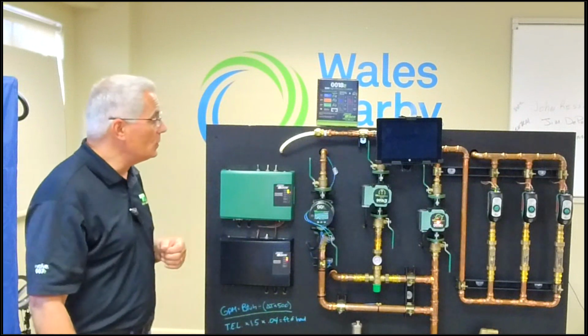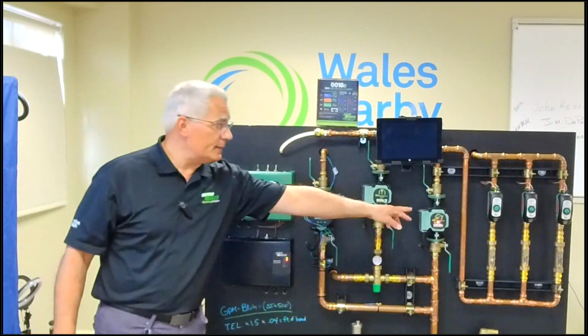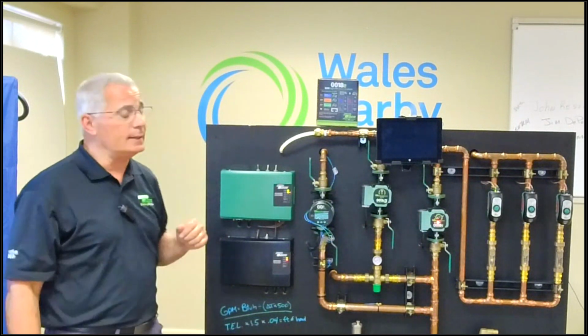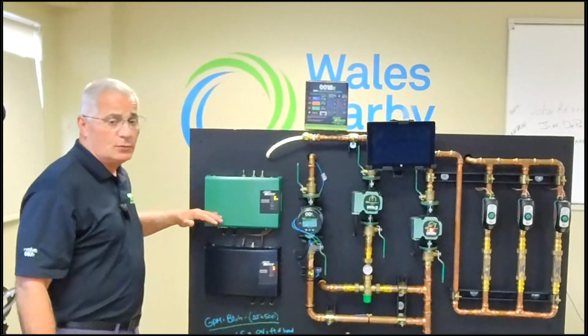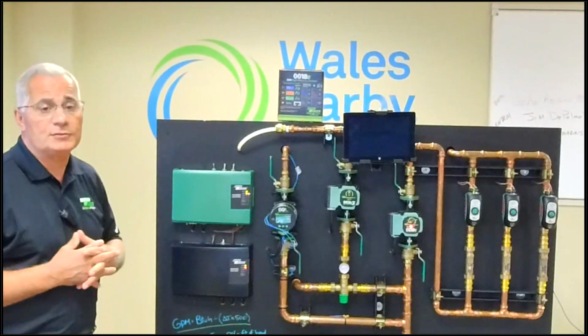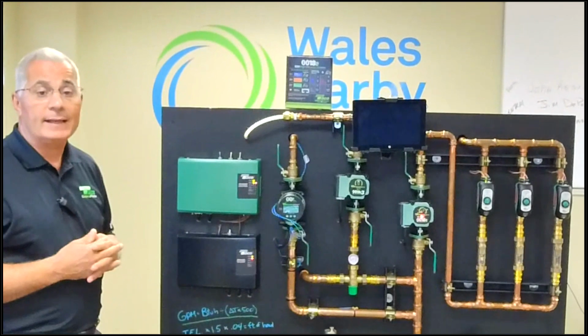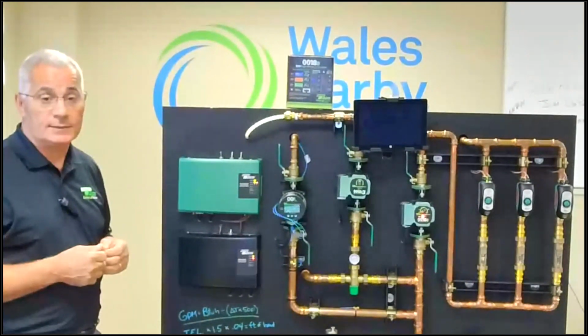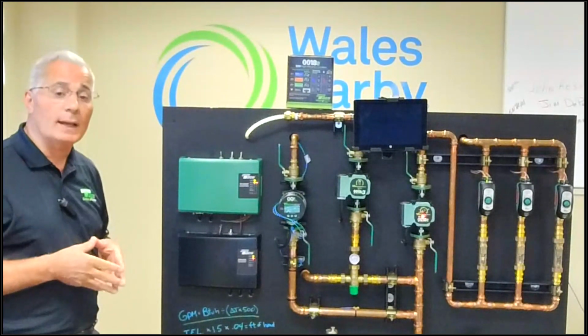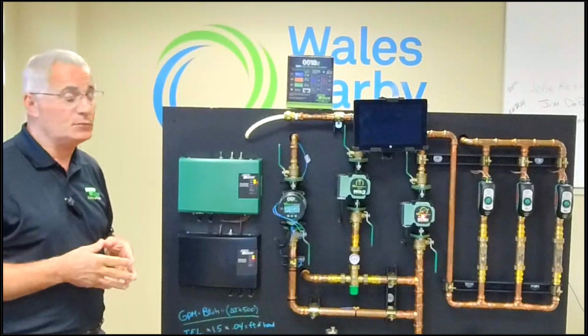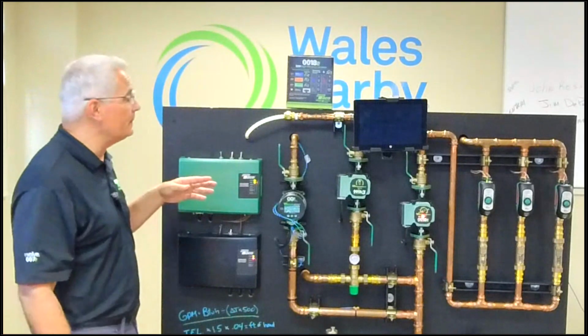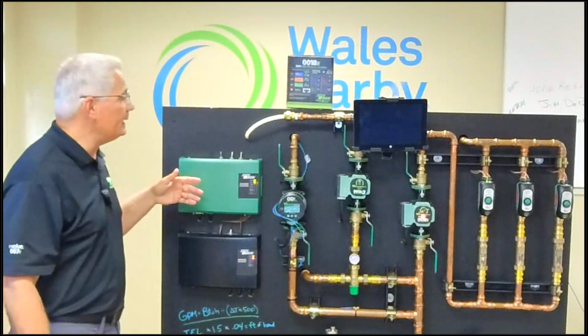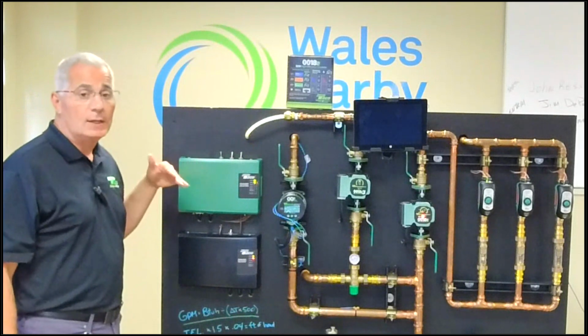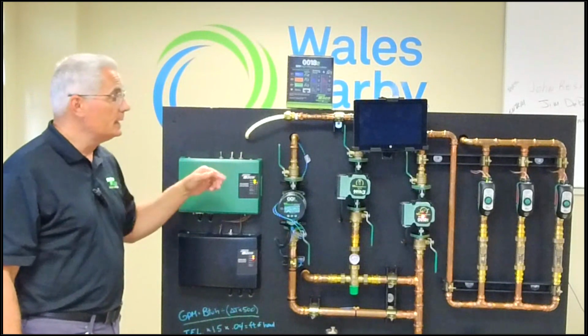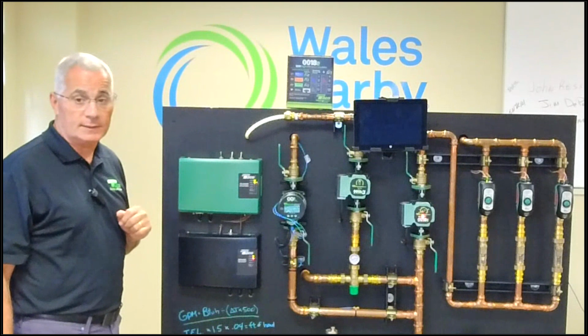So I got one zone calling, and you can see now that the system circulator came on. In the lower left-hand corner of this panel, we do have dry contacts, and that allows you to run up to 3 circulators. So we have this circulator wired to the main pump end switch. Anything on the system that is wired to this panel, anytime anything here calls, we will close that switch and turn on that circulator.